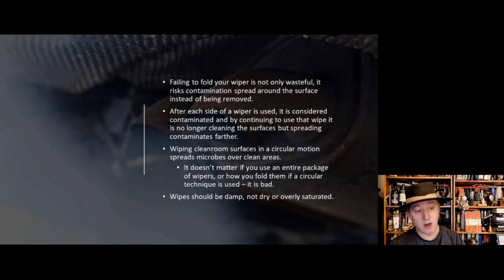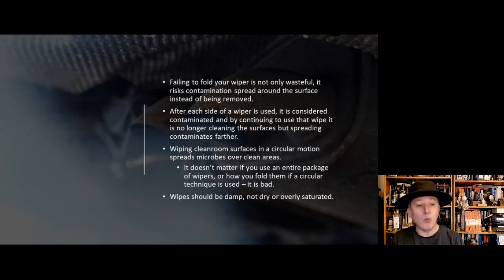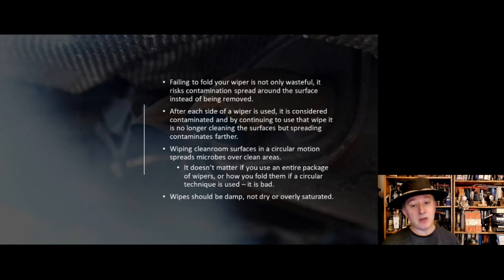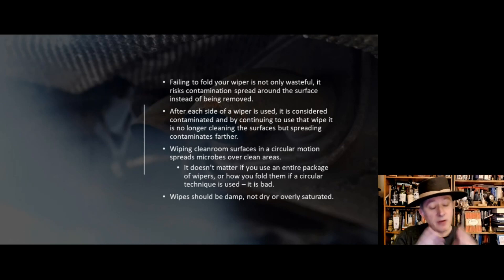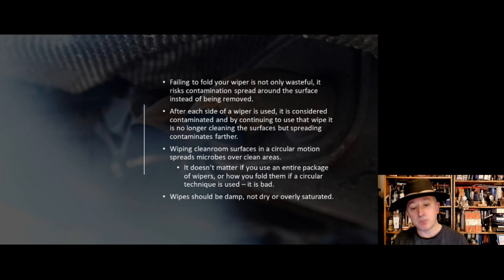There are a number of things to avoid with cleaning and disinfection. We want to practice the folding wipe technique. Failing to use the fourfold wipe technique is not only wasteful of a clean room consumable, it also risks spreading contamination around the surface. Once you've done a single stroke with a wipe, that surface of the wipe is considered contaminated. Continuing to use the same surface just reapplies contamination and potentially increases the microbial presence on that surface.